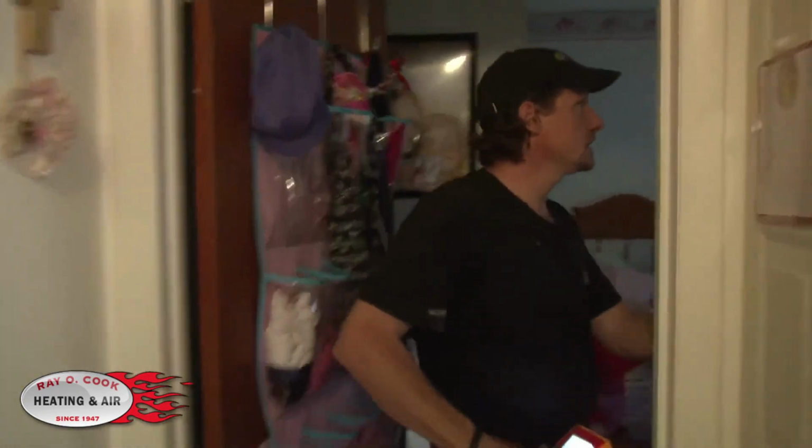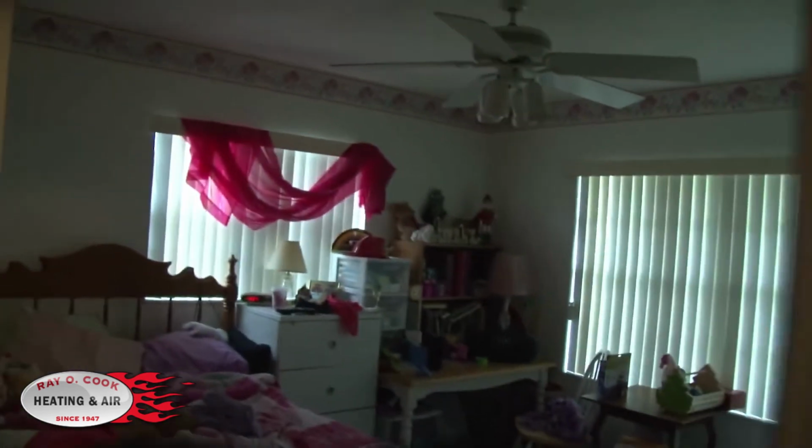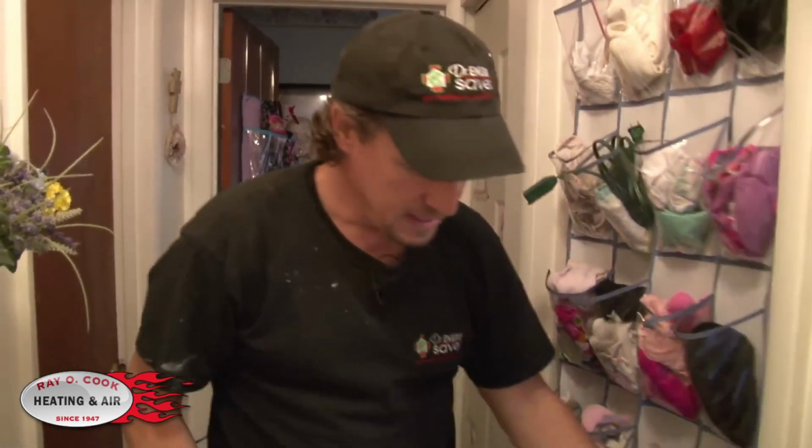So what's happening is the new return that we put in, and you can see it here, that's the return that we put in, is now allowing air to get out of this room back to the air handler so that we don't blow up the room with pressure. When we blow up the room with pressure, because we don't have a return and only a supply, less air comes out of the supply because it's got positive pressure against it, backing it up against the supply duct. Now we have less positive pressure, more air will come out of the supply duct, and that air can get back out of our return duct.